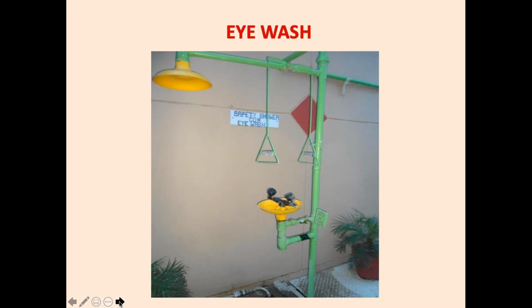Now, the personal safety equipment, what should be kept in the plant room? Eye wash, because eyes are most vulnerable. If ammonia goes into the eye, you can get blindness. So this squirt bottle, a jet spray of water, is important, because as soon as you spray the water, the ammonia will get dissolved and your eyes will be protected. This is an eye wash equipment.